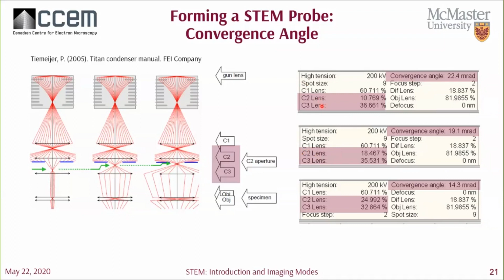In the system, the objective lenses are used for optical focusing, so changing the defocus and focusing the probe on the specimen. Here you'll see that we have a zero defocus in this image, and the probe is focused perfectly on our 1D specimen, which is this arrow. But in reality, you probably will have some sample with some kind of topology to it, and thus we can use the objective lenses to fine-tune the optical focus.